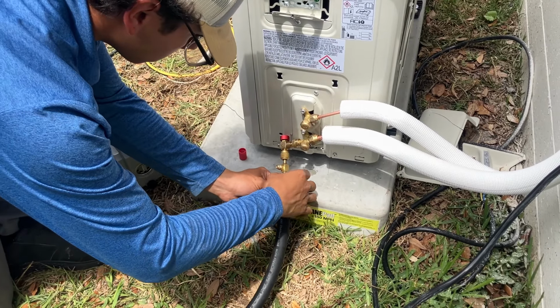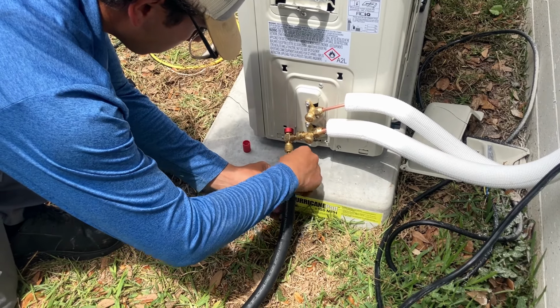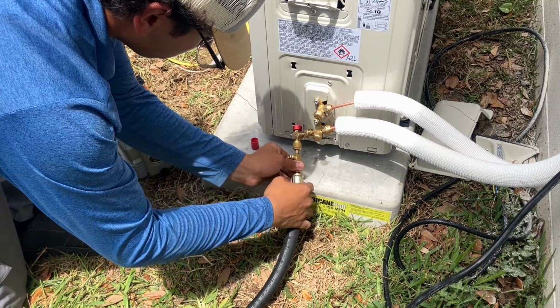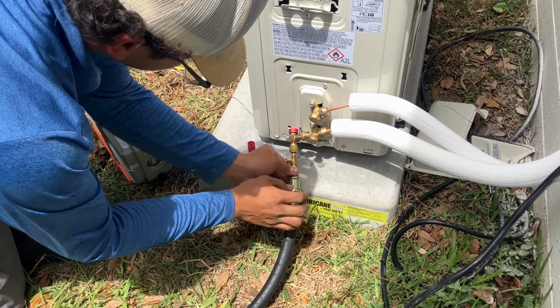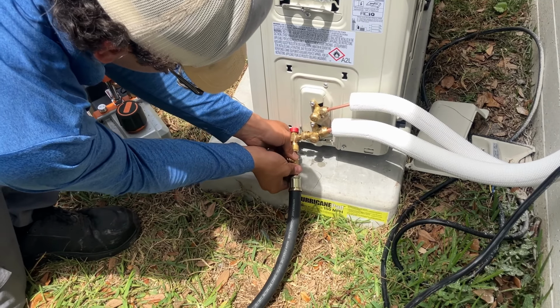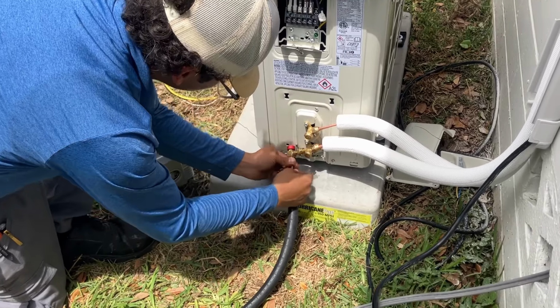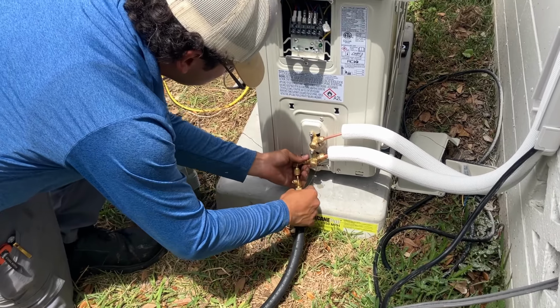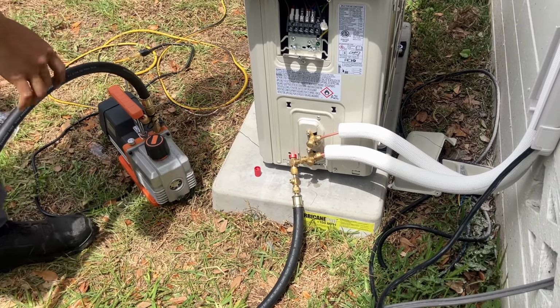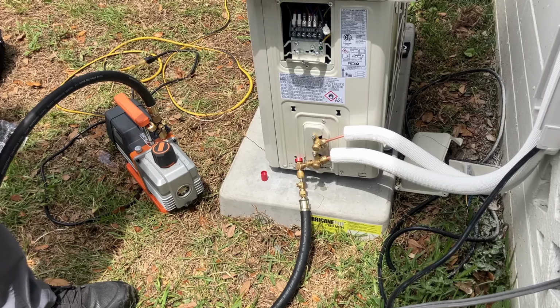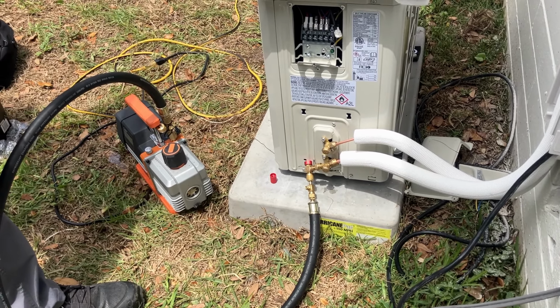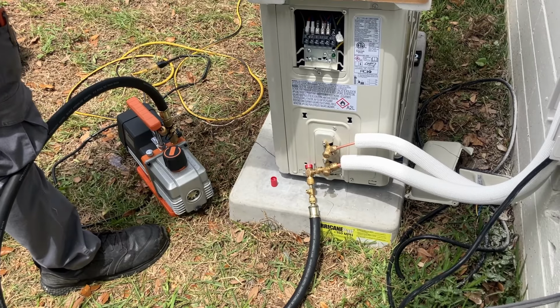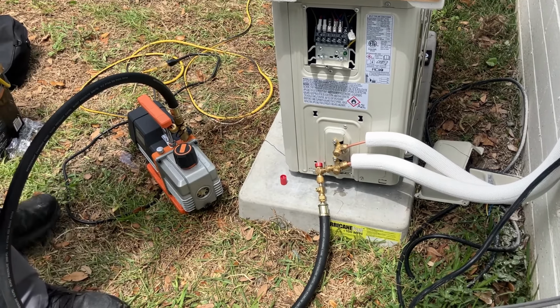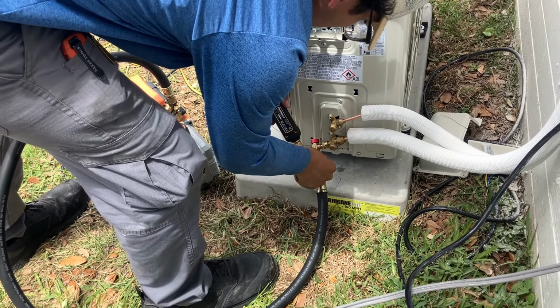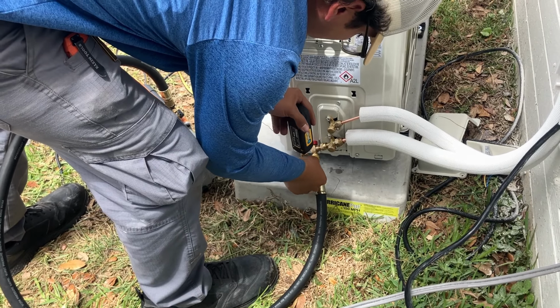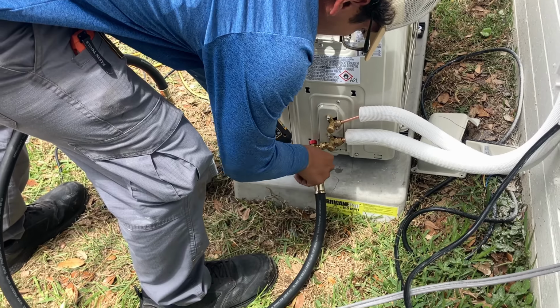It's nice that he has plugs inside the hoses to keep moisture and atmosphere out, because that hinders the time it takes to vacuum down a system. Think about it, folks, when you're pulling a vacuum you're pulling into negative atmosphere, so any moisture in the system is going to boil off. And we know what happens with water when it boils off, it expands like 1,600 times its volume when it turns into vapor, into steam. So moisture boils off and expands, and that increases the time to bring your levels down below 500.